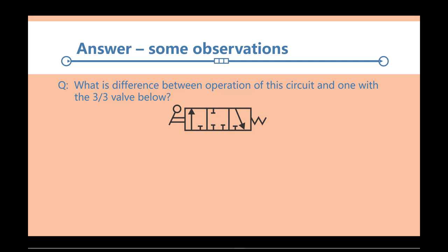So what could happen with this system, or a system, the same system with this valve in it, is the operator could actuate to extend the cylinder, and then somewhere along the way, he or she could make the center envelope active, and that would just lock everything. So that's just a blocking envelope. It blocks the flow from going into the cylinder, but it also blocks the flow coming out of the cap end as it's pushed by the spring. So this would be the retract envelope, this would be the stop or block envelope, and this would be the extend envelope. It's still a three by, it was a three connection valve, but with three envelopes.